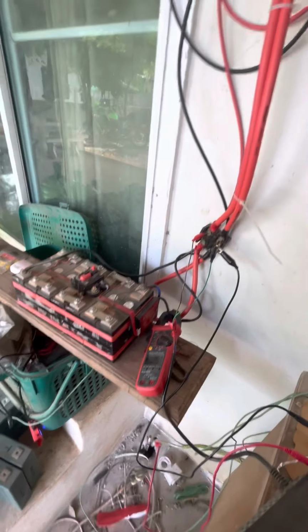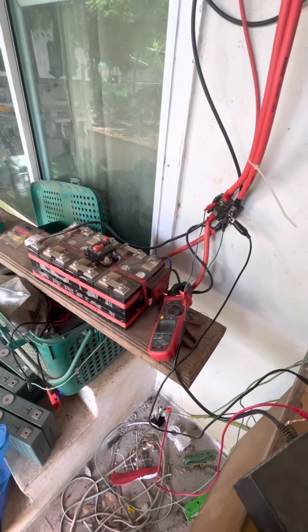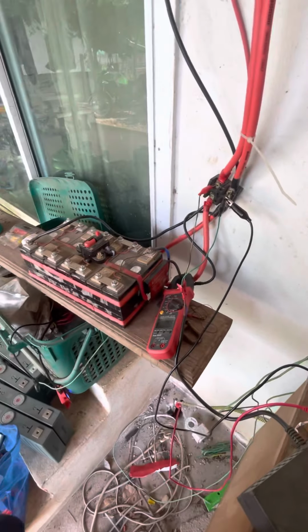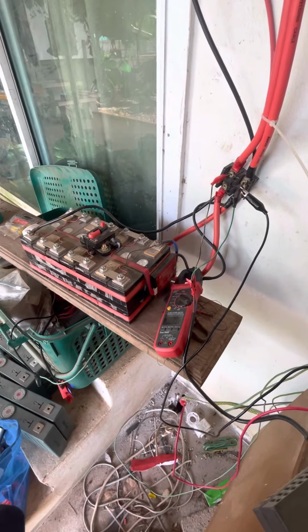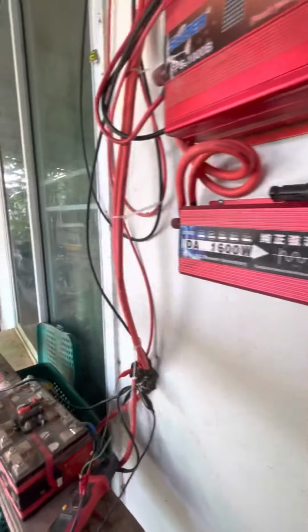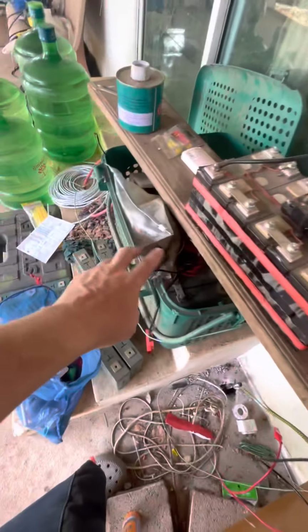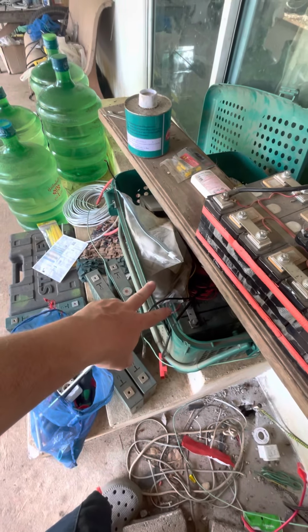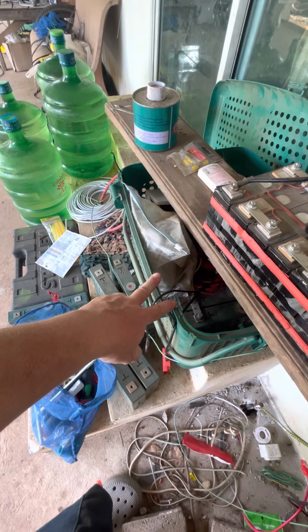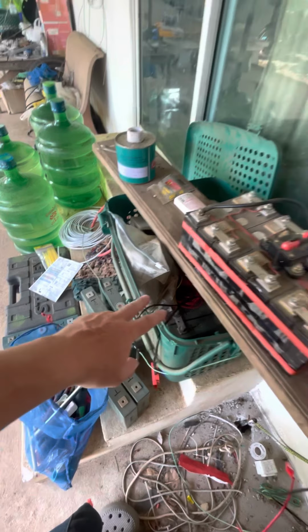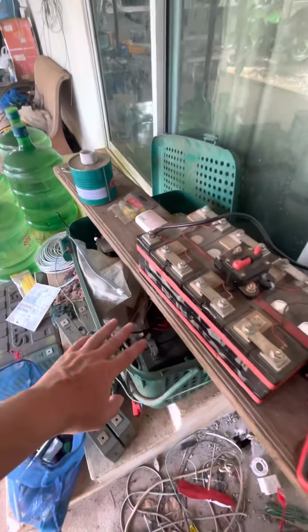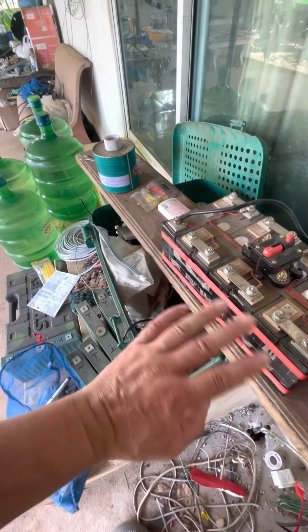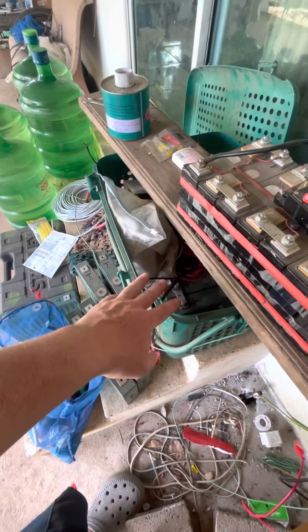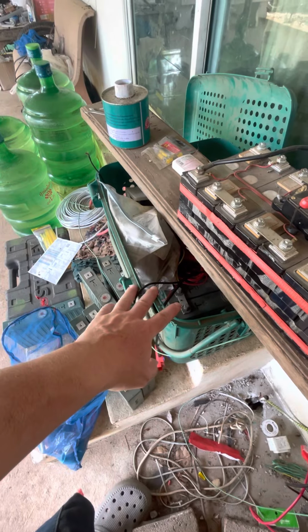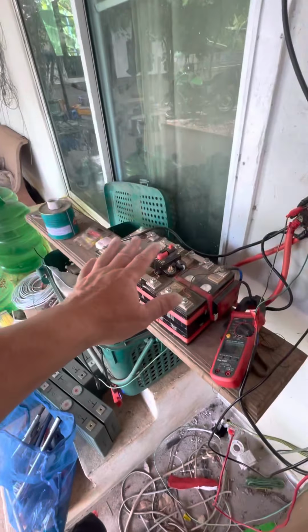Then I've been running it a few times and it kept doing it. I was going, why is this BMS tripping? I looked at the volt, because I didn't put my voltmeter on - I looked at here, that tells me the voltage. So what I did, I turned off the charge and discharge of this on the special, clever BMS. So that battery - I haven't got a separate battery switch - I turn this battery off with those switches, the charge and discharge. So now I know I'm only getting this.